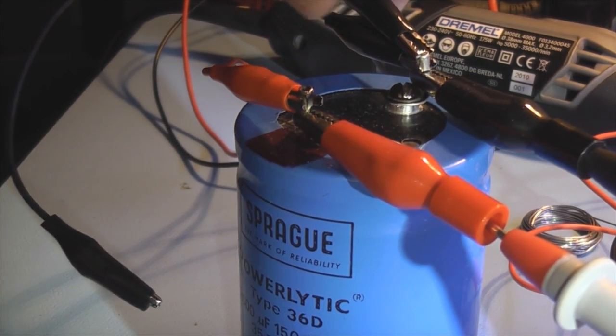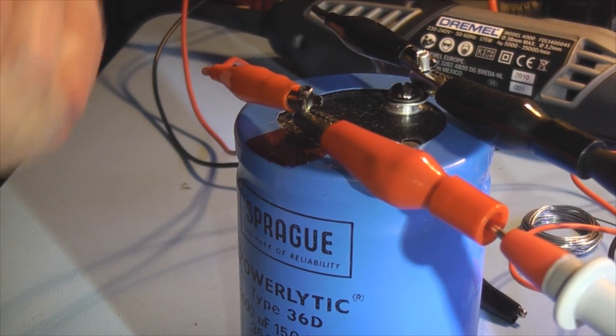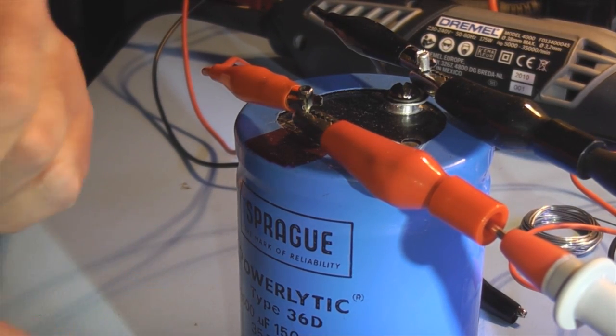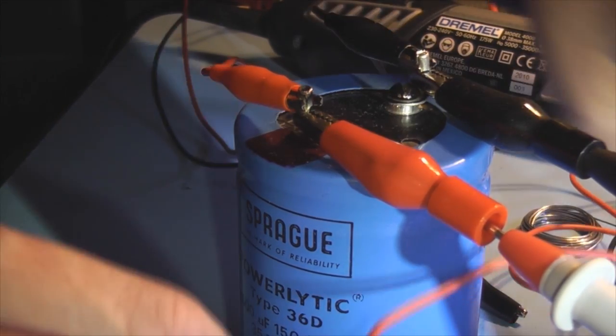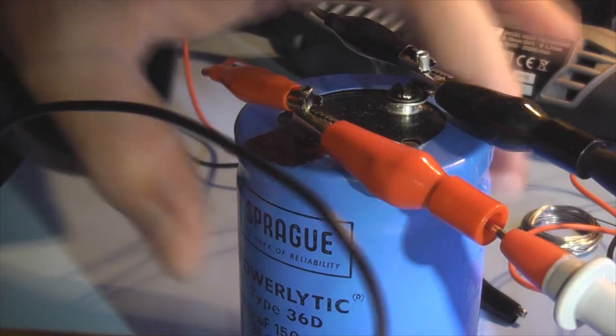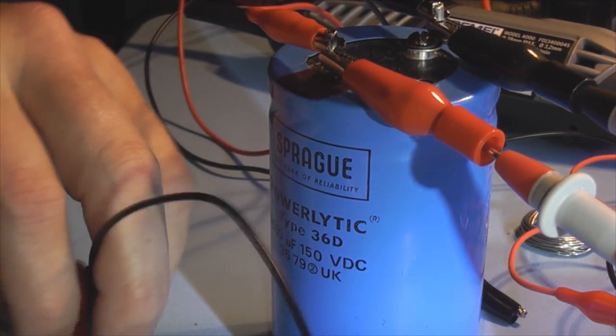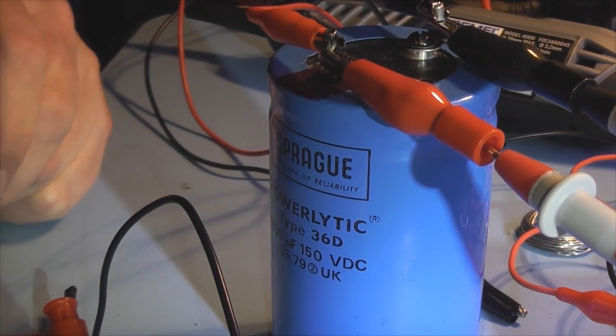Now the reason you do it with a bleed resistor or a capacitor discharge tool is to avoid that massive big dissipation of power. So what you're doing is basically bringing it down slowly, bringing the capacitor down much slower.